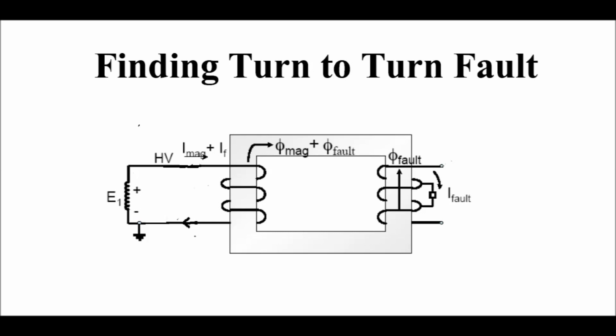But since the secondary winding has an interturn short, a current will flow in the interturn, and that is why a phi fault will flow in the opposite direction of the flux that was flowing due to the current in the primary winding. Therefore the primary winding will draw more current from the supply, and that is I magnetizing plus I fault. By this we can understand the interturn fault in the secondary winding.